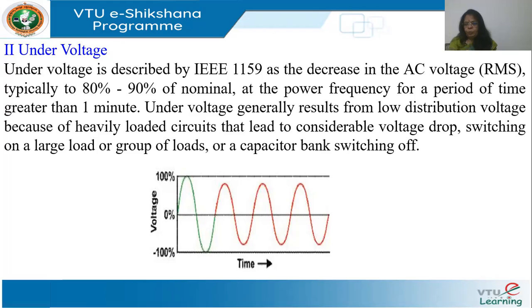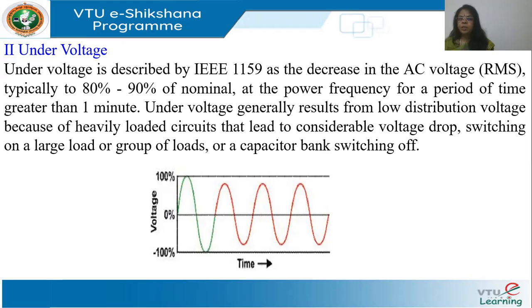Under voltage is the reverse. The IEEE 1159 standard defines under voltage as a decrease in the RMS value to between 80 to 90 percent (0.8 to 0.9 per unit), persisting for more than one minute. It generally occurs on the low-voltage distribution side because of heavily loaded distribution systems drawing large currents, causing feeders to experience larger voltage drops.